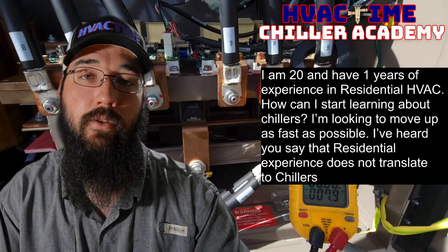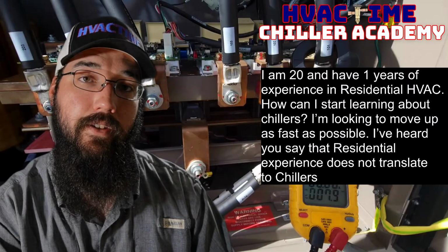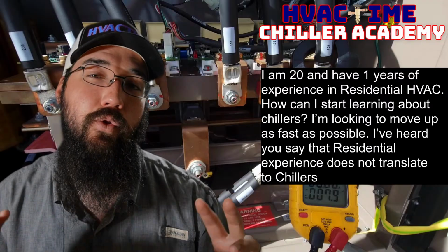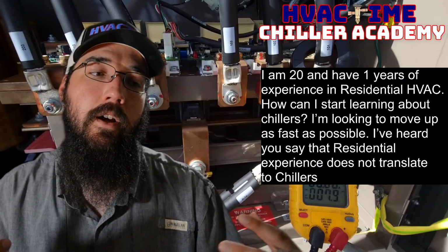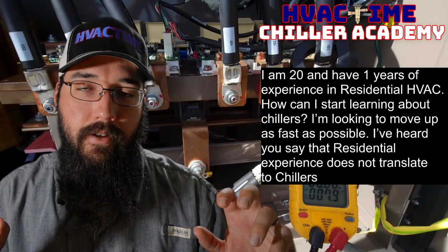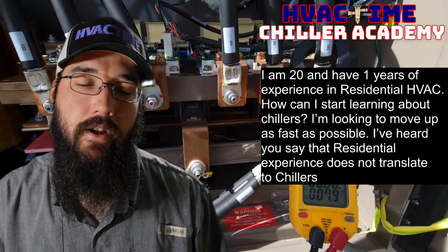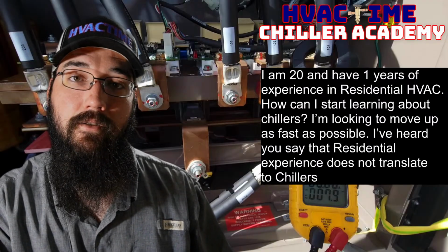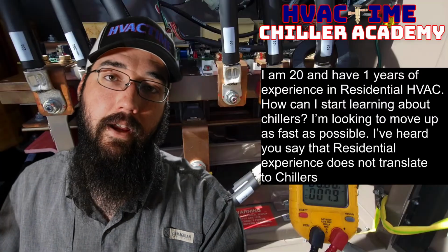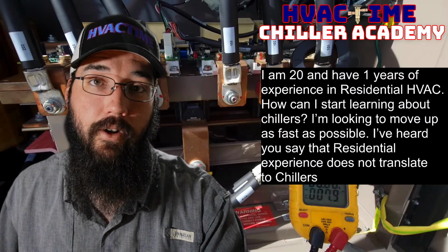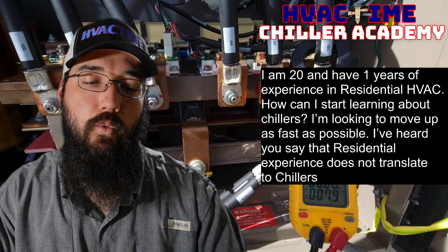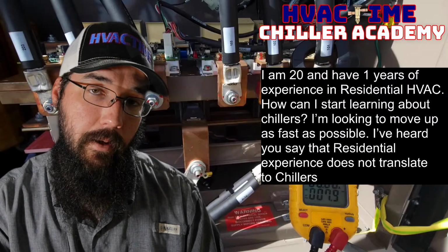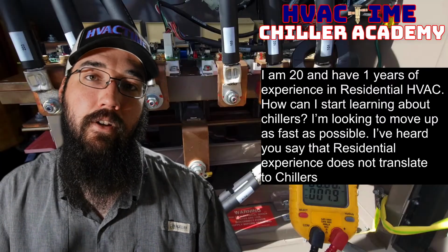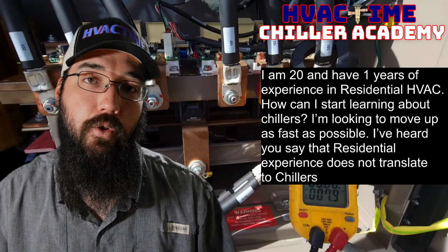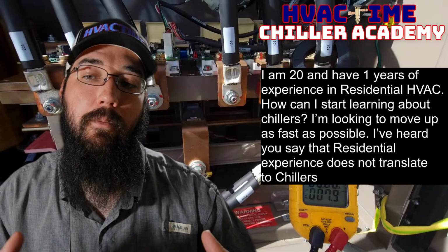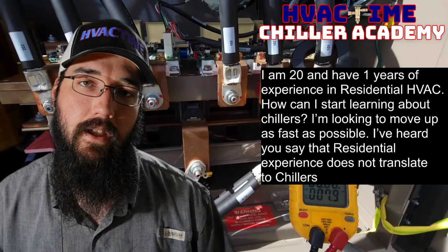These are fundamental operations that happen in residential and in chillers, but we're using slightly different mediums. Mediums are, call it fluid, okay, that is processing through our heat exchanger. The fluid in a split system is air, ambient air that we breathe. The fluid through a chiller's evaporator is liquid water. So we're changing what is flowing through our evaporator, but the core fundamentals of what's happening on a refrigeration level aren't changing. Those things are staying the same. So there are plenty of things from a basics level that correlate.